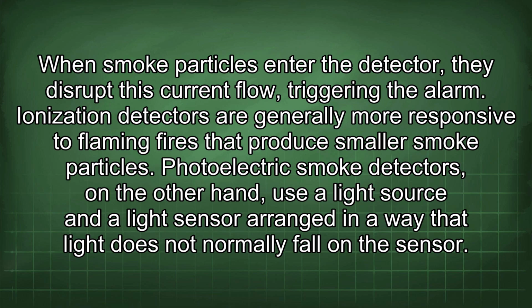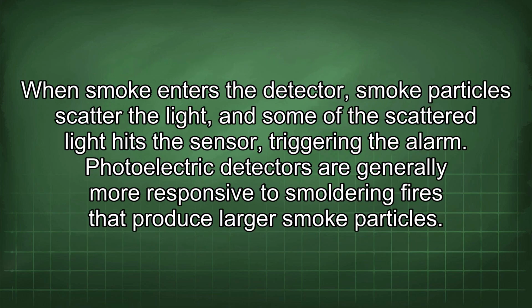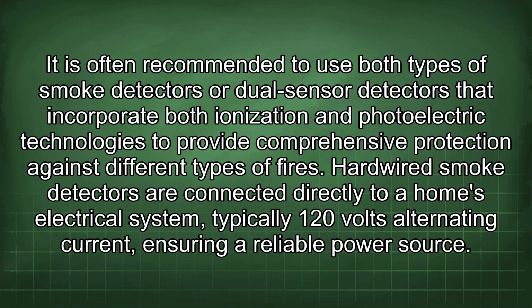Photoelectric smoke detectors, on the other hand, use a light source and a light sensor arranged in a way that light does not normally fall on the sensor. When smoke enters the detector, smoke particles scatter the light, and some of the scattered light hits the sensor, triggering the alarm. Photoelectric detectors are generally more responsive to smoldering fires that produce larger smoke particles. It is often recommended to use both types of smoke detectors or dual sensor detectors that incorporate both ionization and photoelectric technologies to provide comprehensive protection against different types of fires.